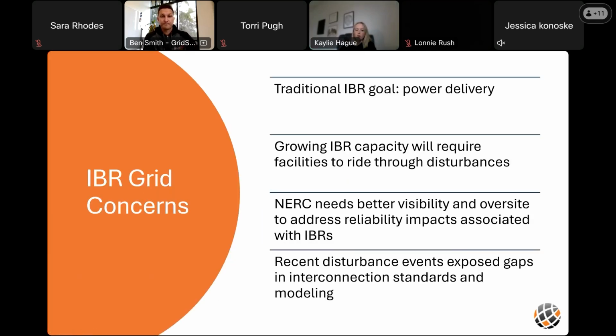So why should we be concerned about all of the IBR that is being connected, or has been connected, and is not registered? Historically, the goal for connecting wind and solar with inverters was primarily just delivering power to the grid. Consequently, grid operators have generally been allowed or even required to disconnect the IBR facilities during times of grid disturbances, and then once everything was cleared, they were allowed to reconnect.